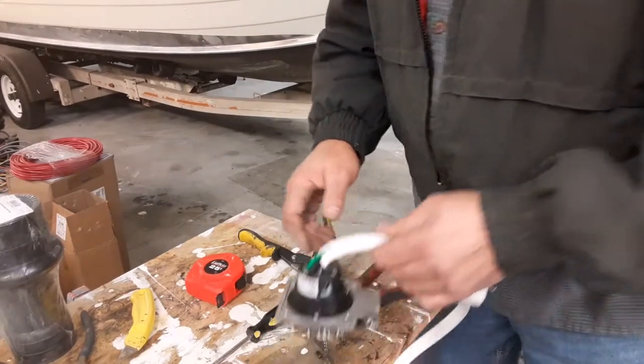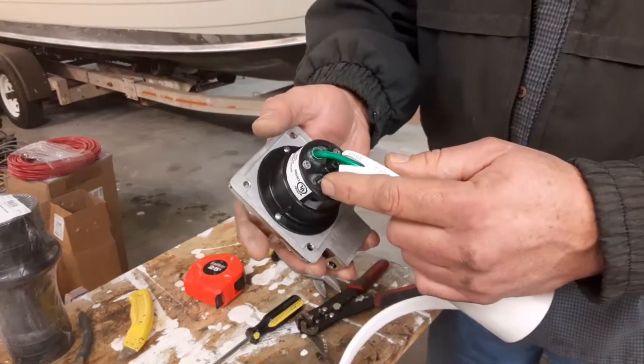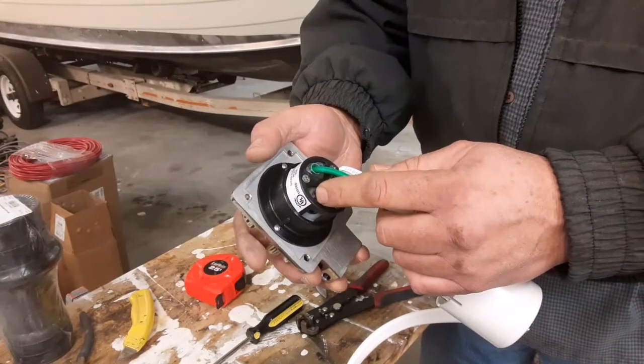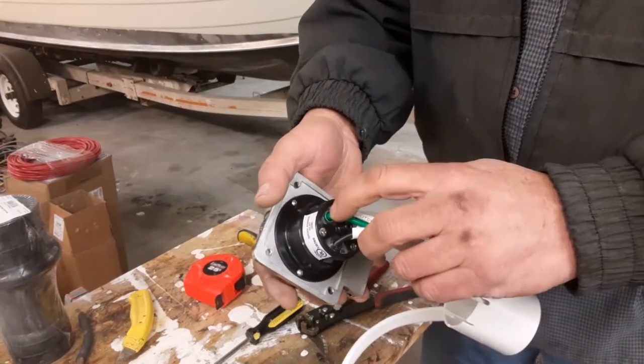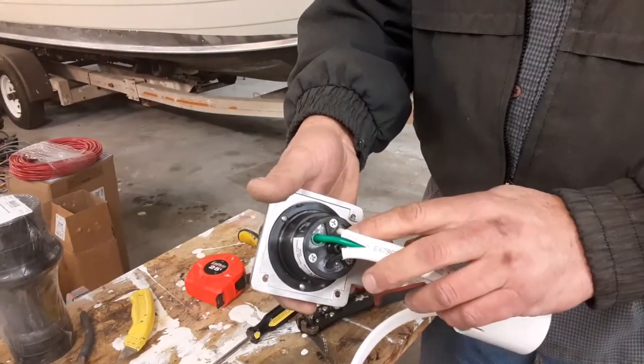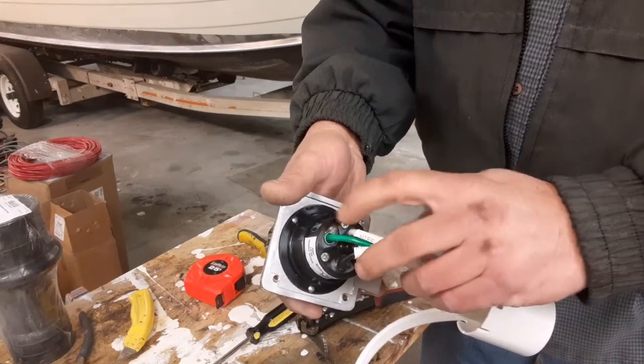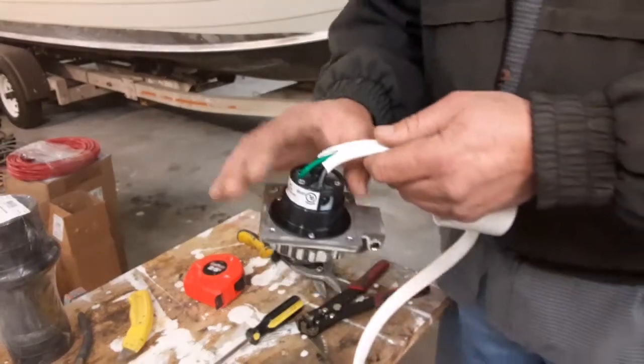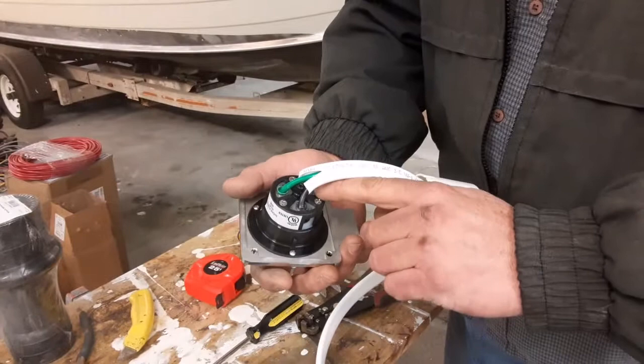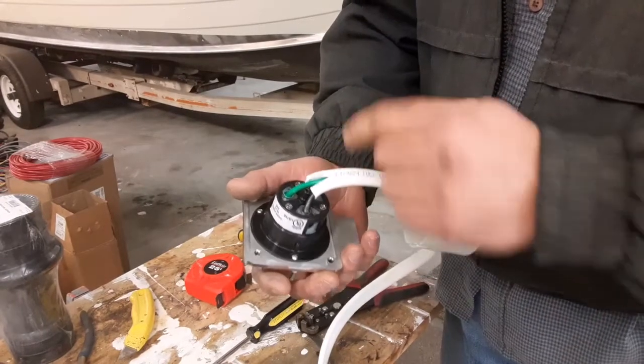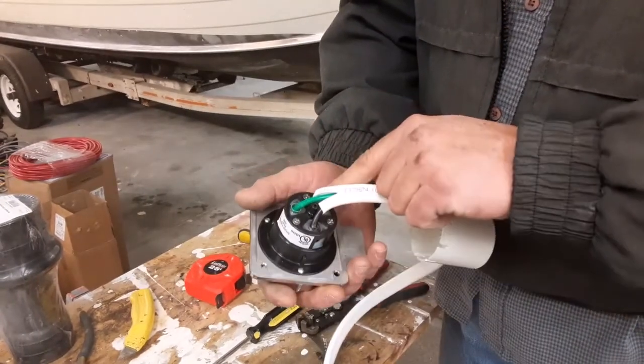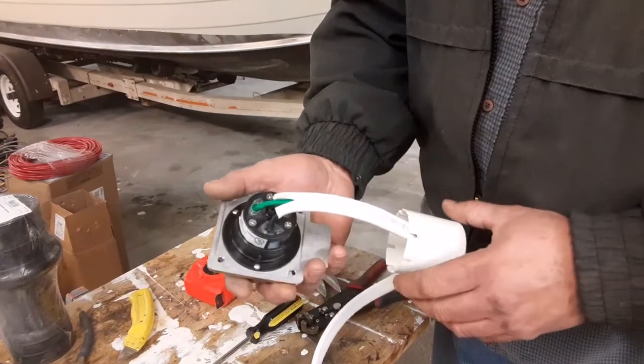In that time, I got the power conductor in. Then we retightened and checked both the ground and neutral at the weatherhead, made sure they're in the proper terminals, and made sure there's no strands hanging out here that could short out or cause a problem.